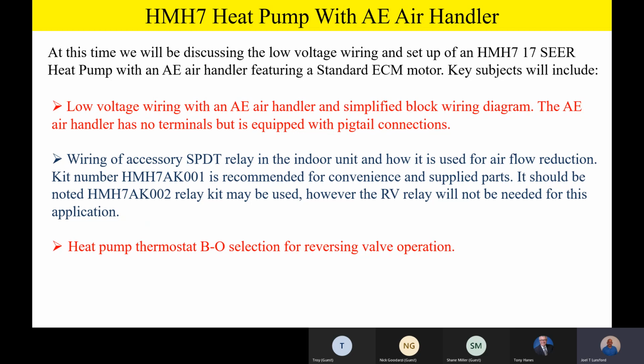So it is recommended. Now, the obvious question comes up. Well, gee whiz, Joel, what happens if we can't get a hold of that kit, or our local supply company is out of them or whatever? And what do I do to hook this up? Very, very simple. Just grab any 24-volt coil, single pole, double throw relay, and you'll have to manufacture some field wiring as far as spade connectors and stuff like that. But you can use a standard peanut relay, and I recommend a sealed relay, but just a standard little peanut relay, single pole, double throw action, 24-volt AC coil, and then you can provide your own biflow filter dryer if necessary. And so please remember that this is recommended.